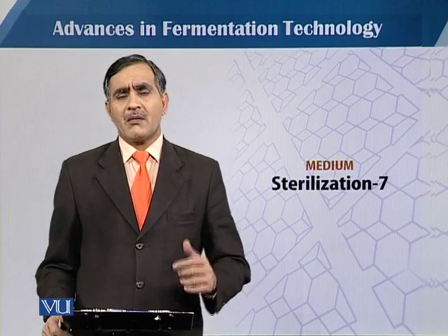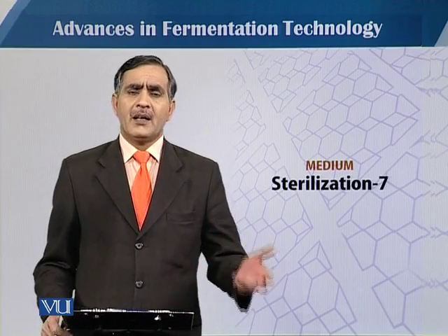In situ sterilization is done on the same place where the fermenter is. So we just supply the steam to the fermenter to sterilize it, and that is known as in situ sterilization. As concerned ex situ sterilization, that is only used at a small scale or shake flask level, because we keep our material or fermenter vessel in the autoclave and then we sterilize. So this is known as ex situ sterilization.